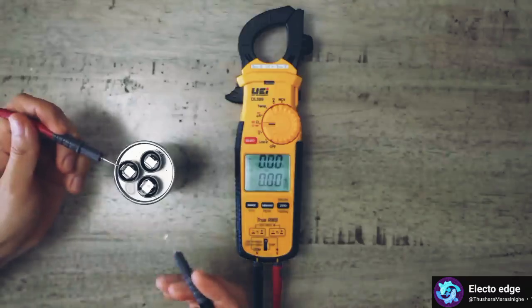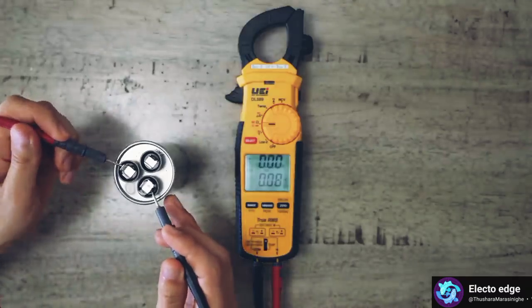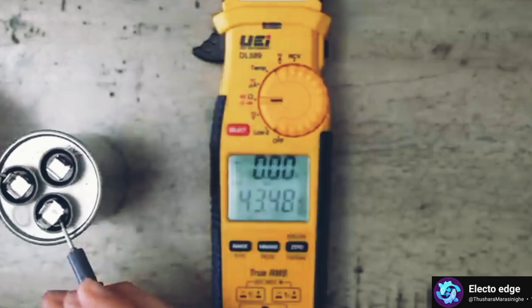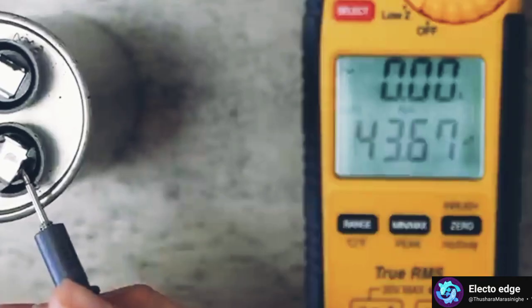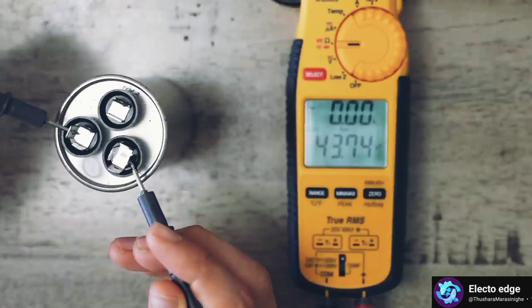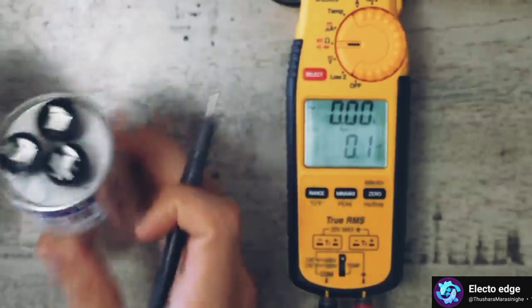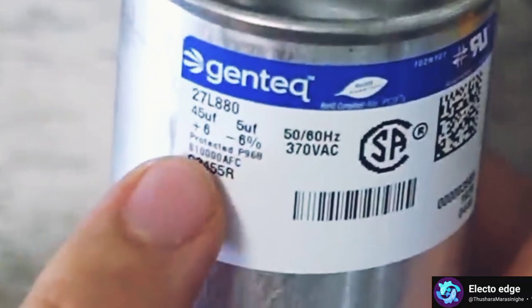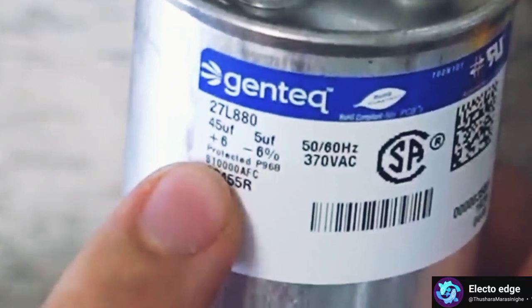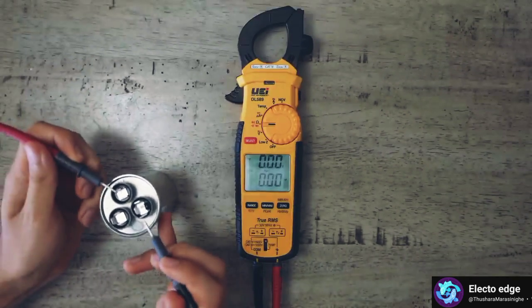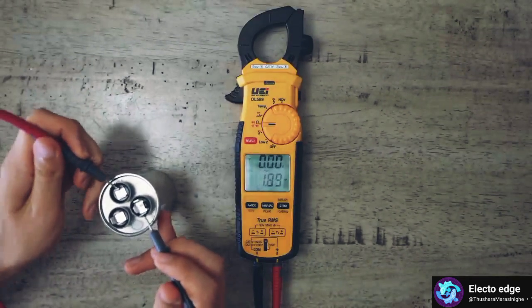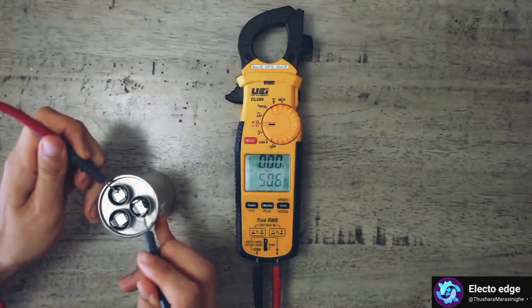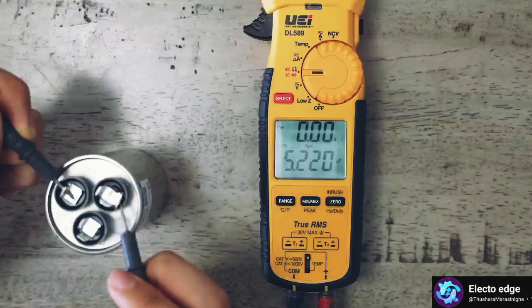Let's start with the larger reading first, which is supposed to be 45. I am getting 43 microfarads, which is pretty good. I believe this one is still in range because it's plus or minus 6% from the 45. And if we check the smaller reading, we should be getting somewhere around 5 microfarads. Usually if the capacitor is bad, the reading will be much lower than the rating.